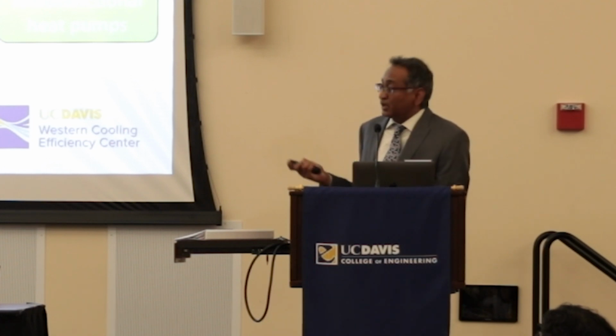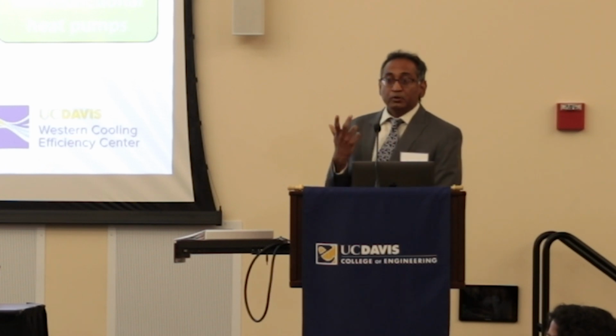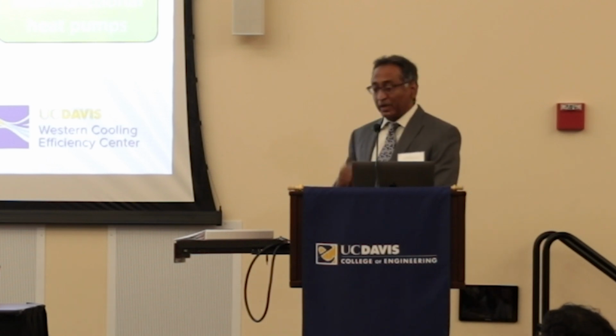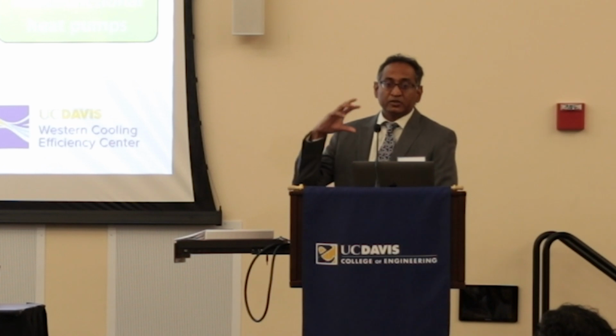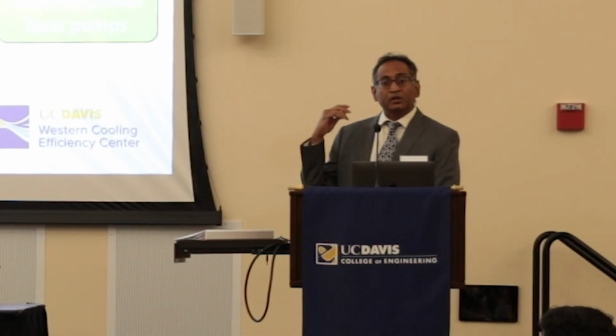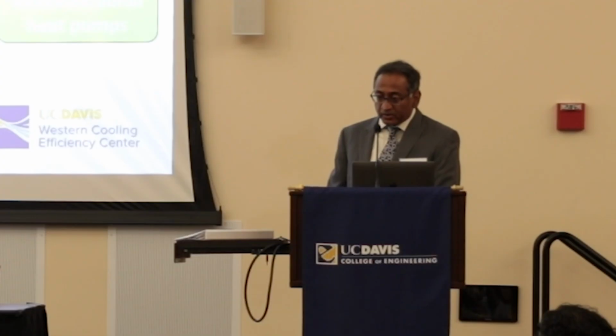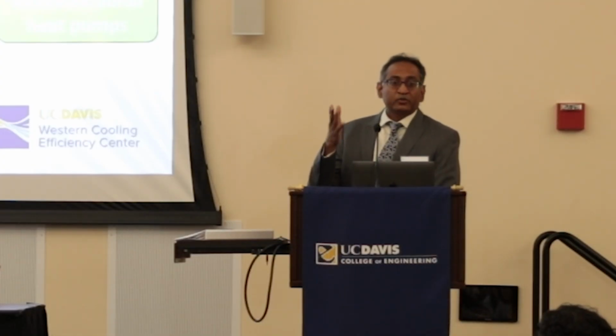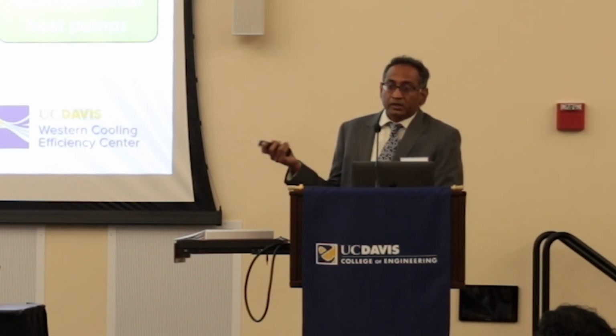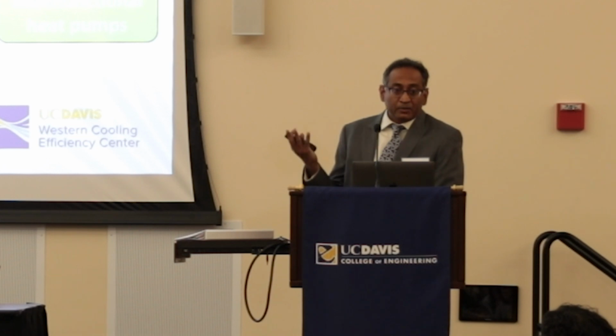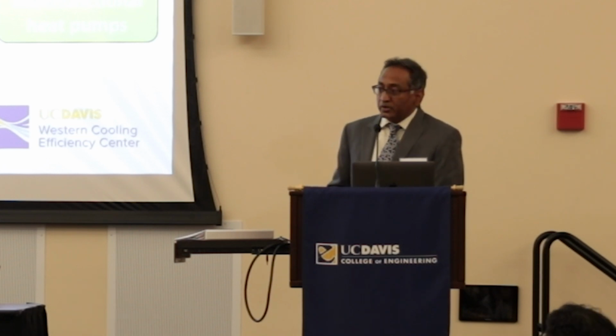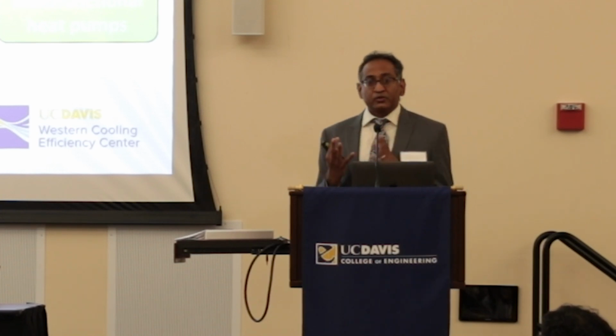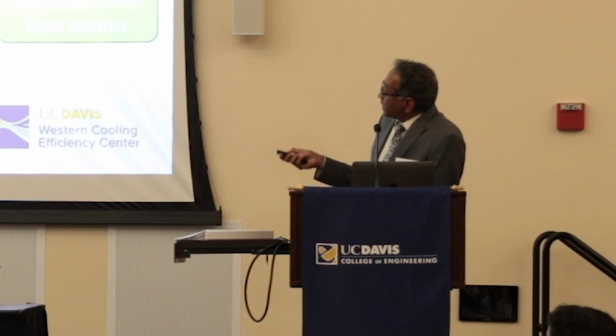So if you look at those barriers, the first barrier is that you need to have increased electrical panel capacity, and that's a big barrier for heat pump adoption. The reason you need electrical panel capacity is that, unlike with a traditional air conditioner, you can't just swap one out for a heat pump, because during the cold winter times you need an increase in electrical capacity by way of strip heating. Let's say the outdoor is really cold, the outdoor coil will get iced up, and you need to reverse the cycle to defrost it. And when you do that, you're running an air conditioner during winter. Not nice. So you've got to provide strip heating to keep the occupants warm. And that tanks efficiency, and you need that extra panel capacity for the strip heating. So that's a big downside.